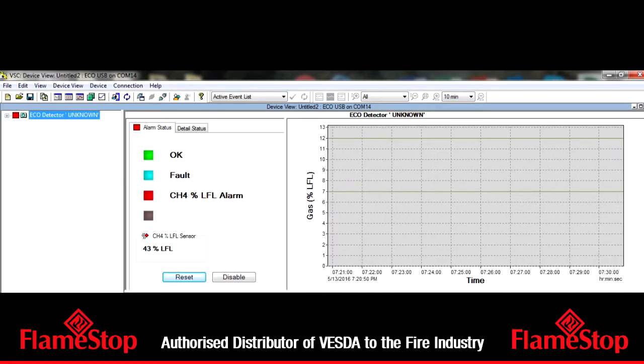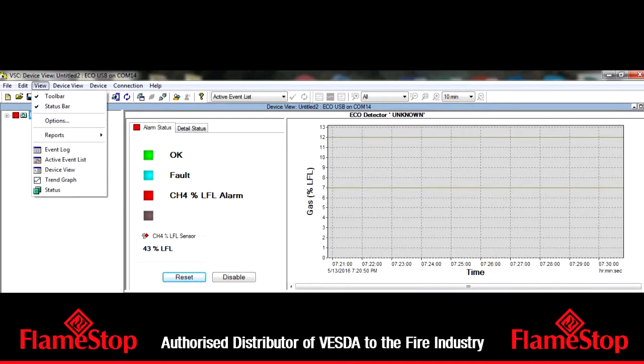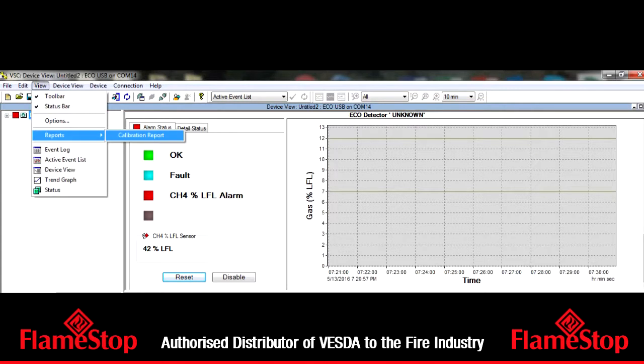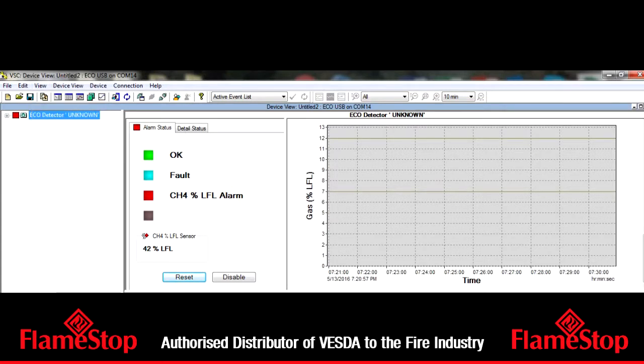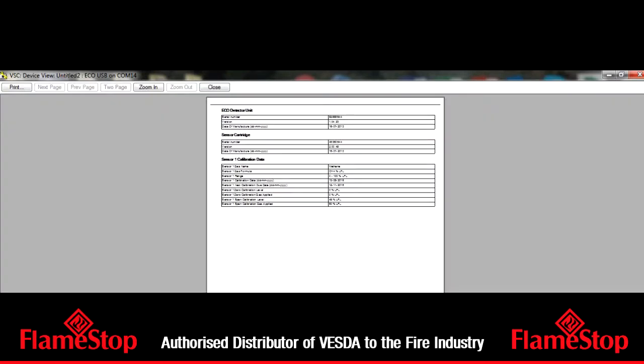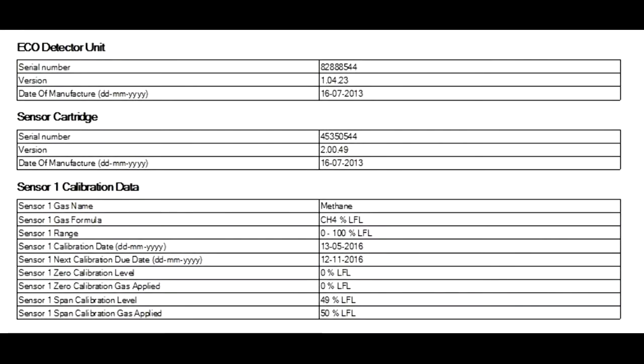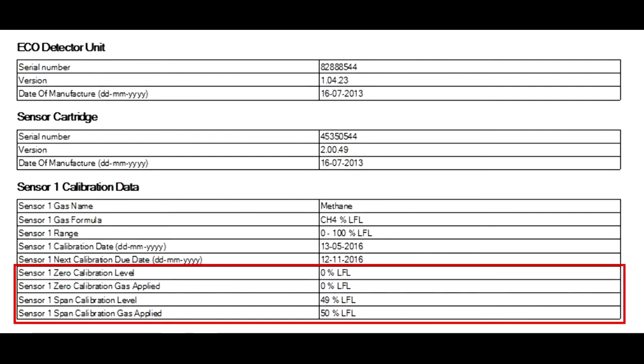Highlight the detector, then go to View. Go to Reports, then select Calibration Report. This will generate the calibration report. The top of the report contains detector-specific information. You must verify the span gas calibration level is within 10% of the gas applied. If not, you must recalibrate the detector.